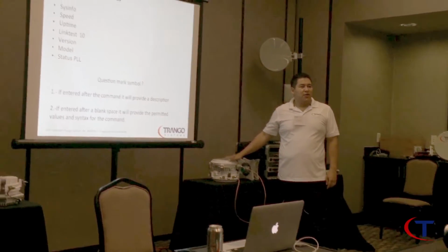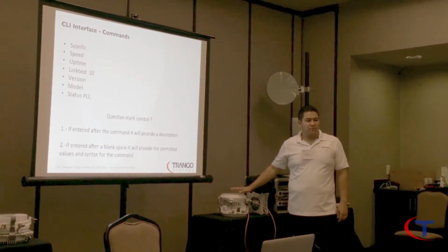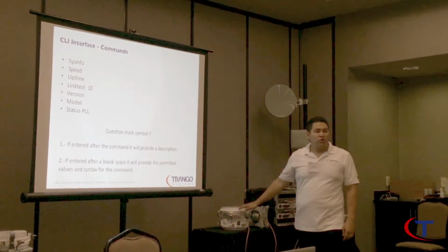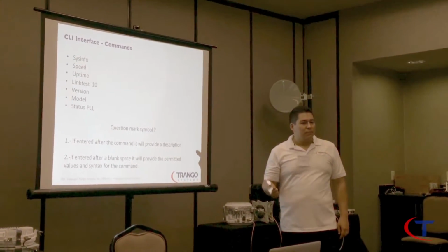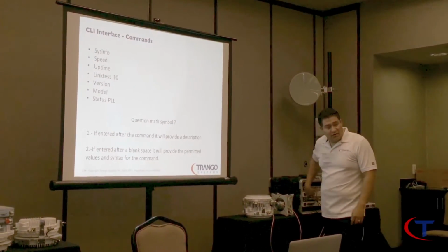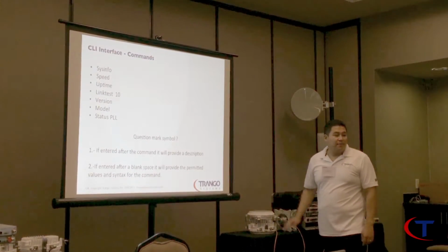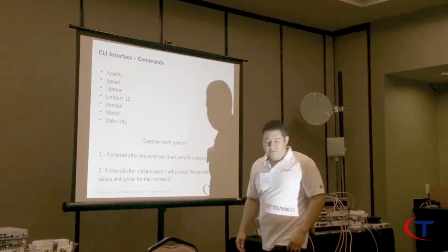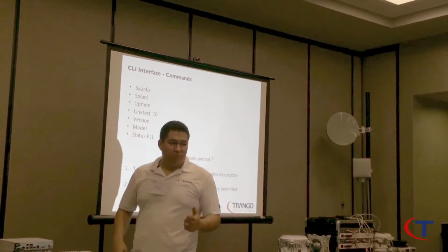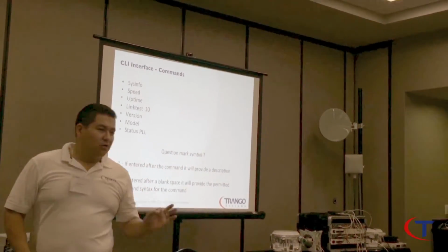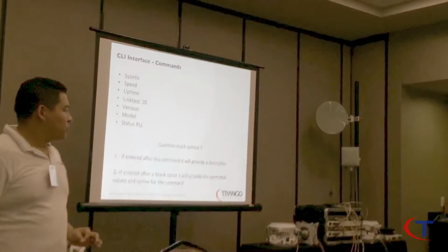It's just going to tell you no information, no information. So you know at that point you either have an IF problem, an N connector problem going from the IDU to the tower, or literally your ODU went down. Could happen: lightning strike, bad IF connector. The model command is going to be one of your best friends as well.